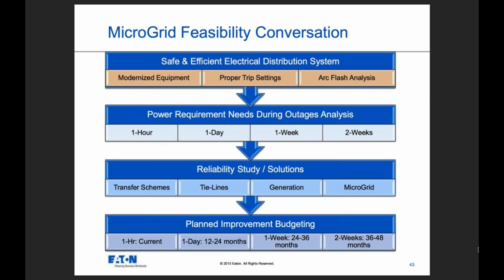Things like arc flashes, if you have circuit breakers tripping that shouldn't trip, you may need a study, or you may need to upgrade the trip systems. So you want to take a step back and not spend money adding things and then have something fail.